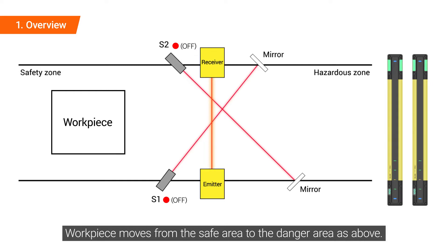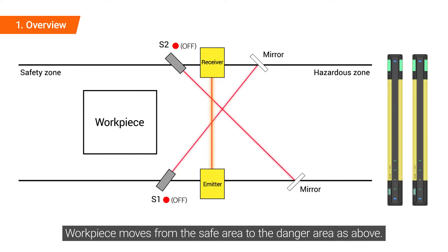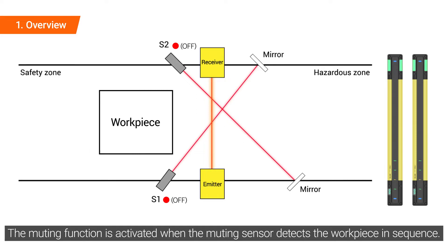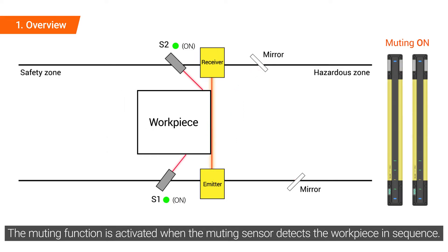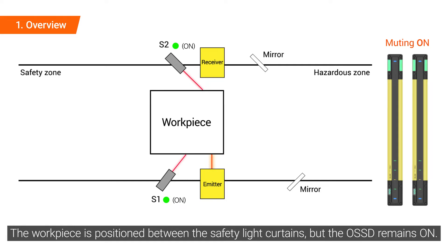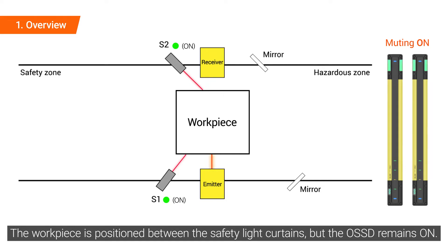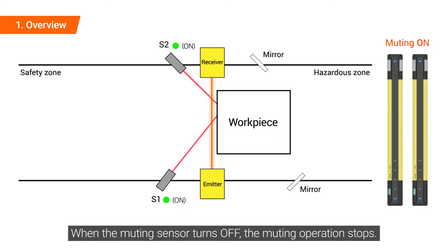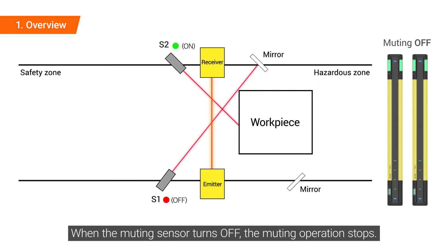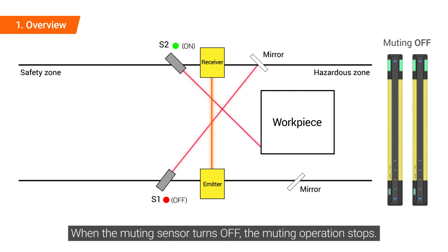The workpiece moves from the safe area to the danger area. The muting function is activated when the muting sensor detects the workpiece in sequence. The workpiece is positioned between the safety light curtains, but the OSSD remains on. When the muting sensor turns off, the muting operation stops.